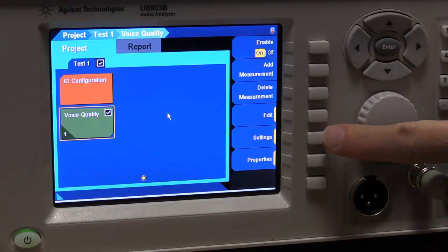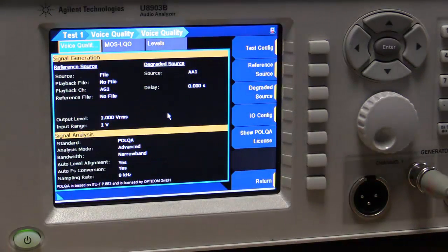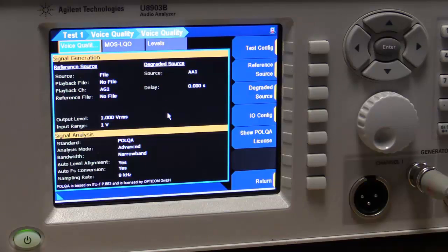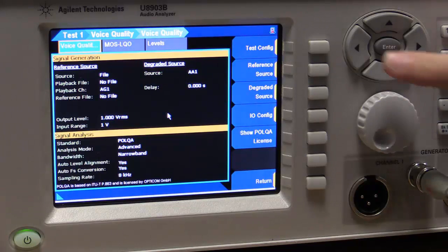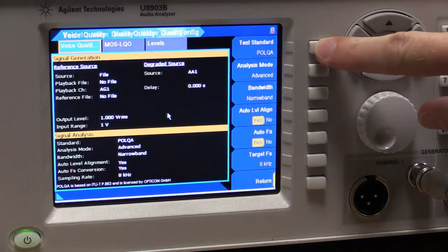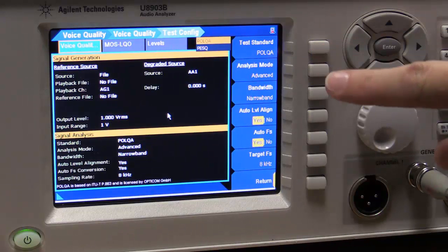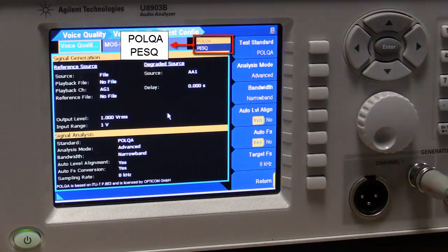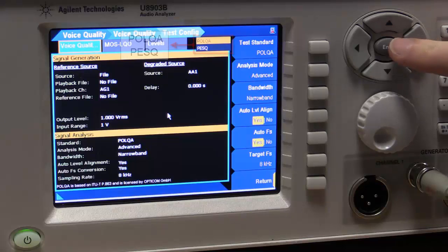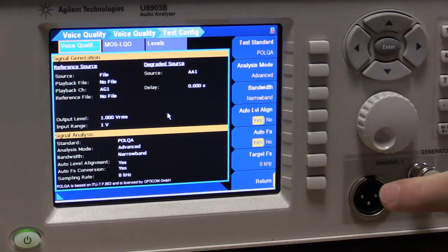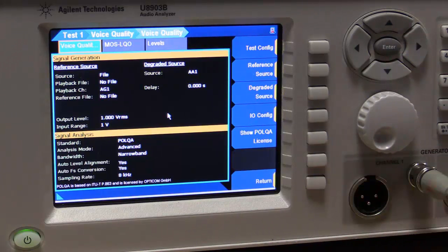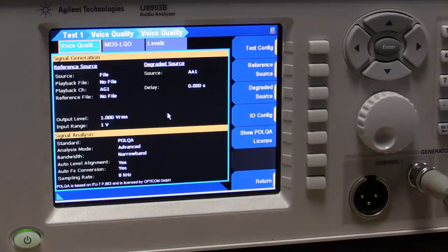We can then go in and set the individual parameters of that. So the first item we might be interested in is the actual standard we're going to look at here. We've got the choice of PESQ and POLQA in here. So we're going to choose a POLQA measurement. And we go back there.